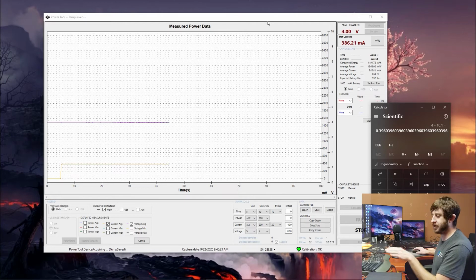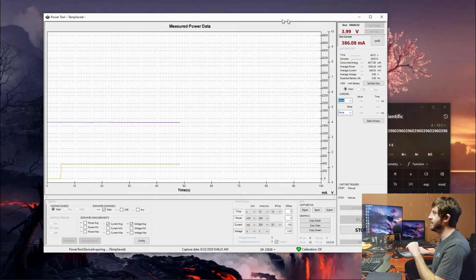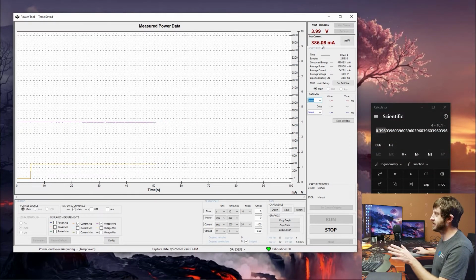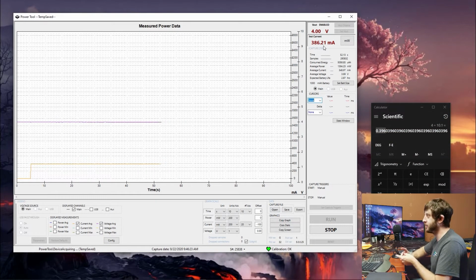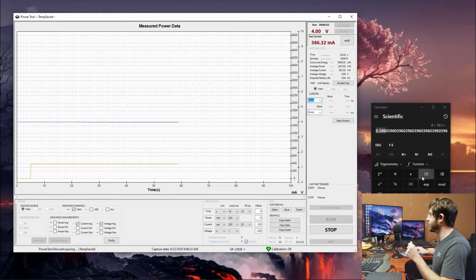And so this power monitor, I've intentionally set the calibration a bit off just for demonstration. And so these values on the coarse channel, you're going to want to be within 1 milliamp or 1%, whichever is greater. So we're quite a ways out of spec on this particular channel.